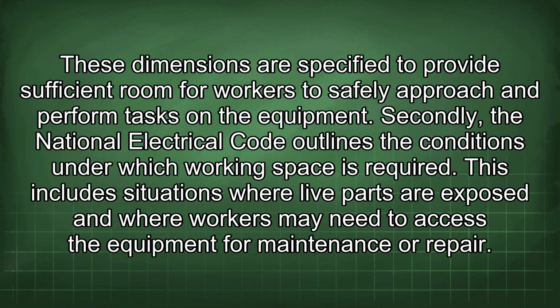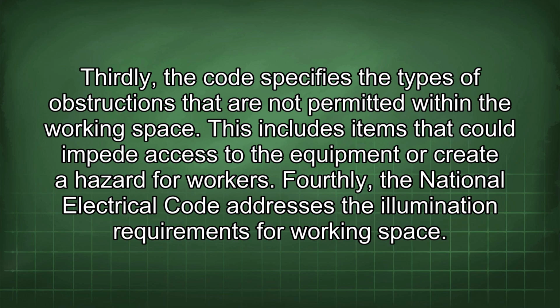These dimensions are specified to provide sufficient room for workers to safely approach and perform tasks on the equipment. Secondly, the National Electrical Code outlines the conditions under which working space is required. This includes situations where live parts are exposed and where workers may need to access the equipment for maintenance or repair. Thirdly, the code specifies the types of obstructions that are not permitted within the working space. This includes items that could impede access to the equipment or create a hazard for workers.